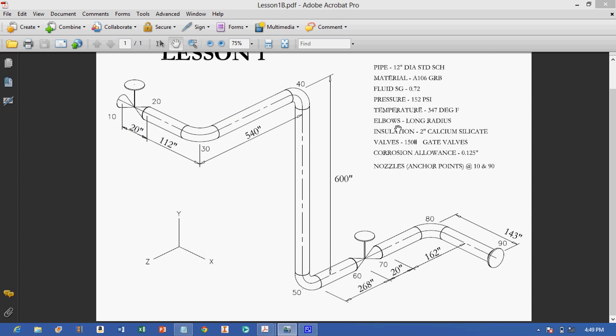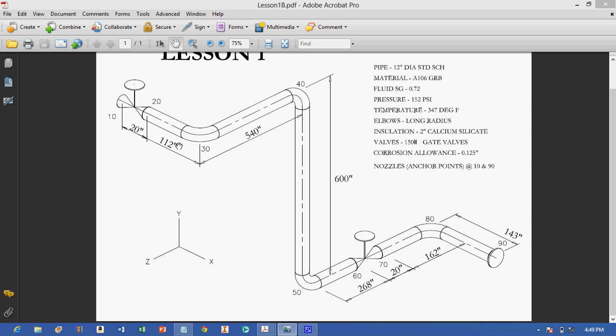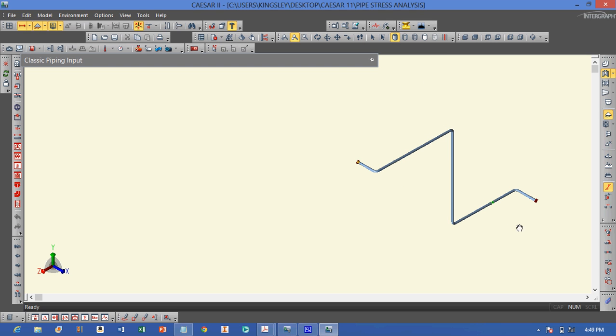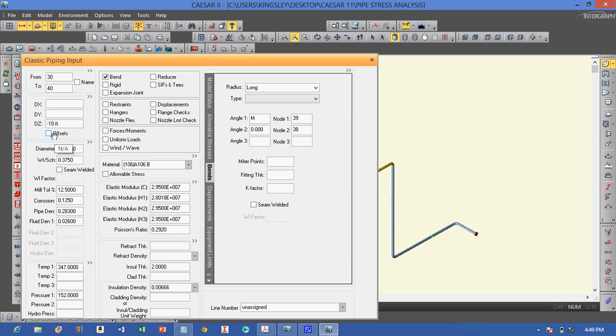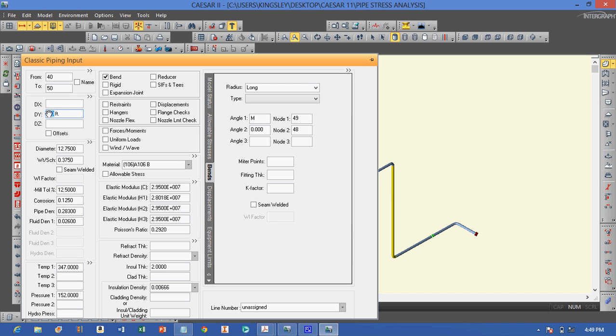This is where engineering judgment comes in. We go back into our inputs to see what we can do about those stresses from node 20 to node 50 and from node 70 to node 90. If we reduce the pipe length here — let's say to 10 feet — and reduce this other length to 20 feet, that might reduce the stress. Let's try that and click run again.